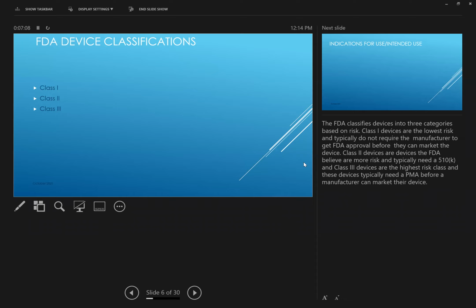Great, thanks. The FDA also classifies devices, and they're based on risk. So class 1 would be the lowest risk class. Class 2 is, quote unquote, a medium, and class 3 is the highest risk class. Those classifications basically give you the indication of how much work the manufacturer has to do. A class 1 device doesn't require pre-market approval or pre-market clearance. You hear the term pre-market clearance. Class 2 requires FDA pre-market clearance, and that's typically a 510K type submission.